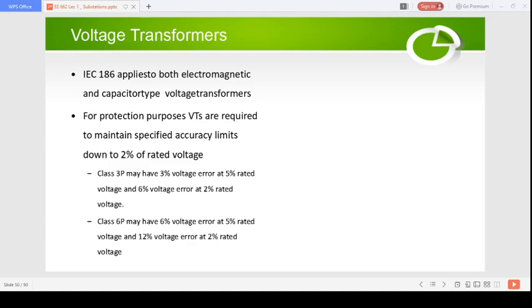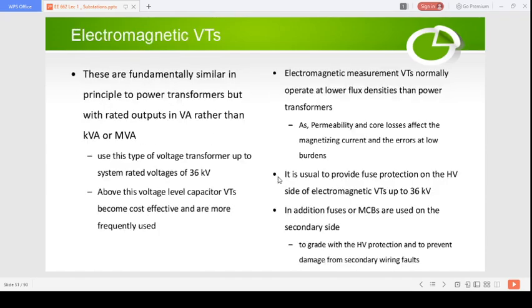So the class 3P may have 3% voltage error at 5% rated voltage, and 6% voltage error at 2% rated voltage. And the class 6P is defined in such a way that it may have 6% voltage error at 5% rated voltage and 12% voltage error at 2% rated voltage.